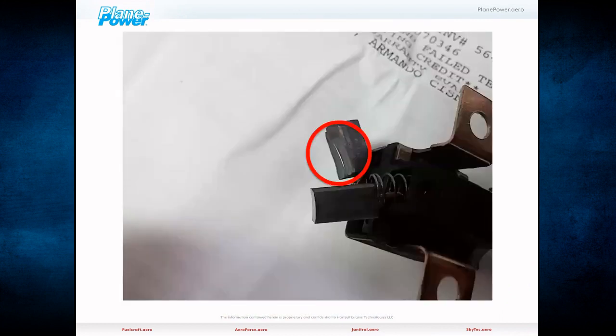Notice this one. The brush block was pulled out, for whatever reason, maybe to check the brushes or something like that. It looks to me like when it was put back in, they didn't do it properly. Technically, you're supposed to take the brushes, push them down inside the brush block, and insert a little piece of wire, like a paper clip, through there in front of the brushes to hold them in place. Then you reinstall the brush block assembly. Once reinstalled, you pull that pin, the brushes snap up against the slip ring, and you're ready to go. This looks like somebody had the brush block out and did not know what they were doing.